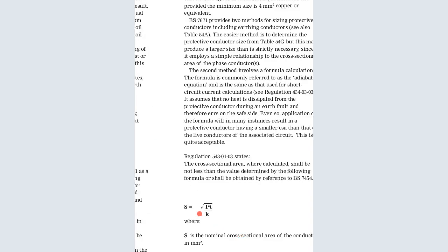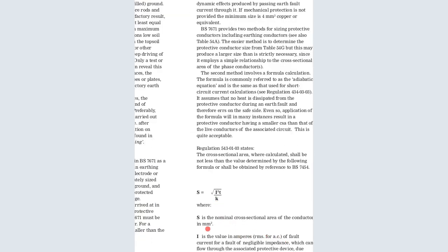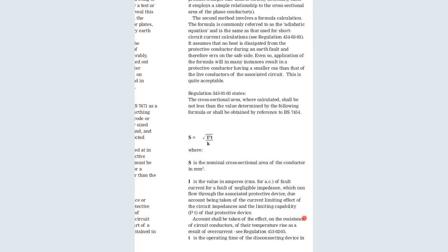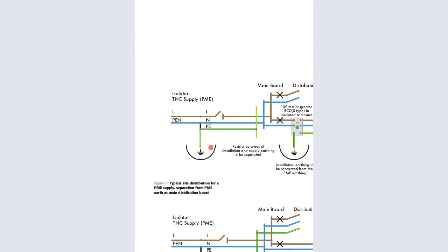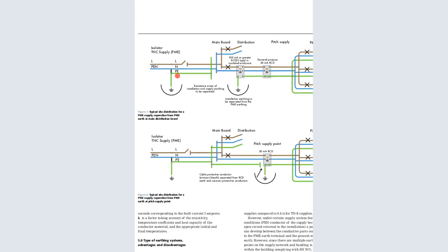The formula used to calculate the size of the conductor is I squared t equals k squared S squared, where S is the nominal cross-sectional area of the conductor in square millimeters, and I is the value in amperes of the fault current for a fault of negligible impedance which can flow through the associated protective device, account being taken of the current limiting effect of the circuit impedance and the limiting capability. Account shall also be taken of the effect on the resistance of the circuit conductors of their temperature rise. And t is the operating time of the disconnecting device. When all these are factored in, you will be able to know the size.